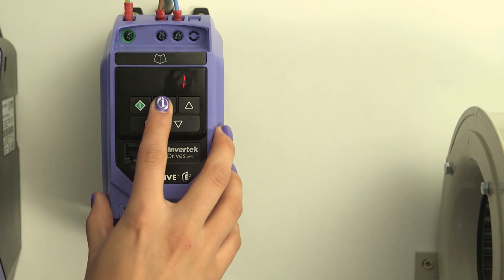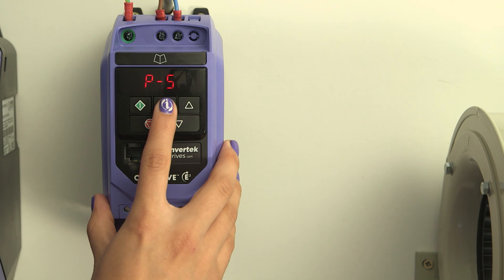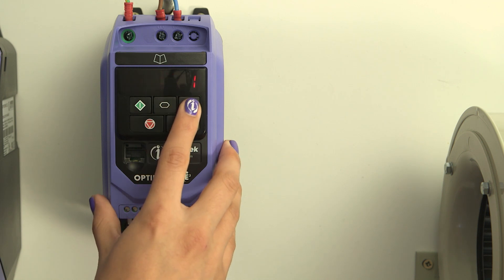In the E3, there are just a few more parameters compared with E2, and the motor parameters begin at P51, which selects the different control modes. Here we will set it to 3 for brushless DC motor control.